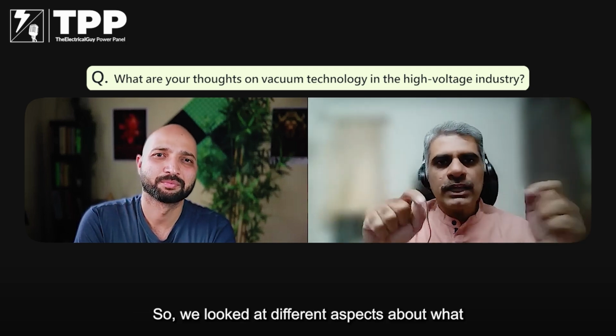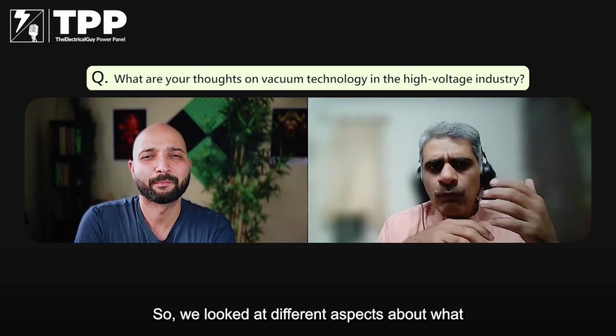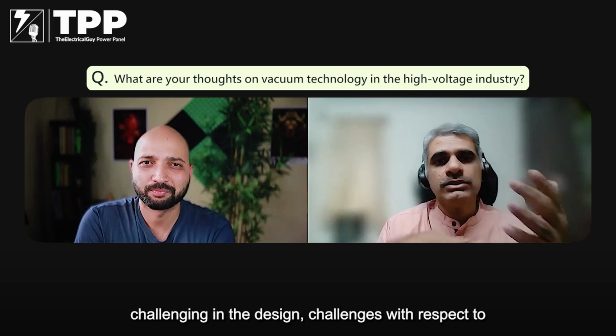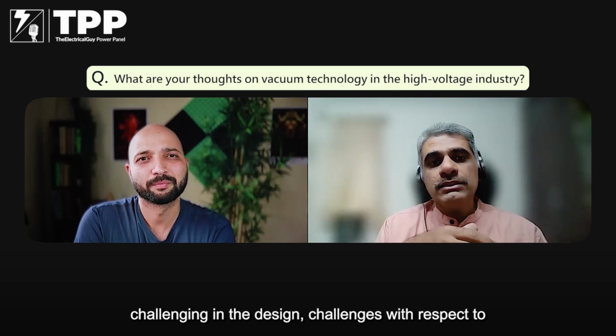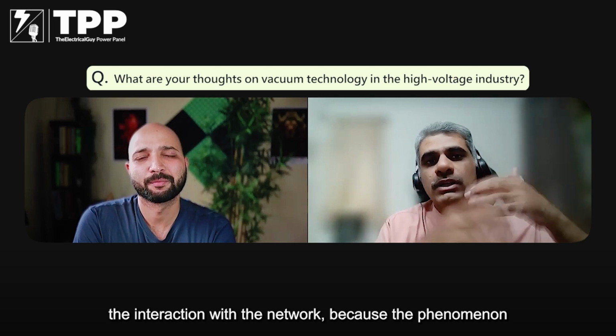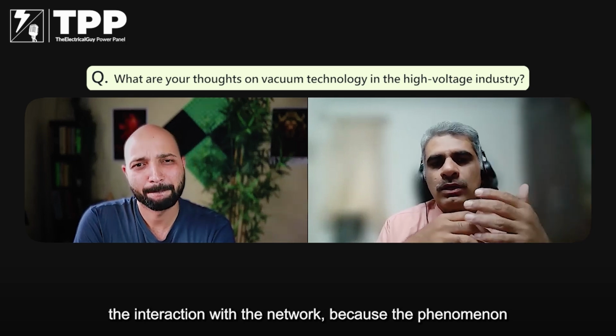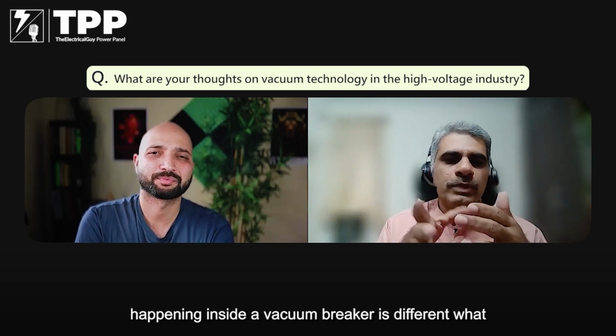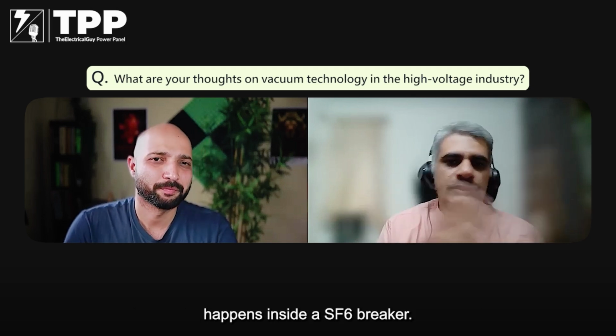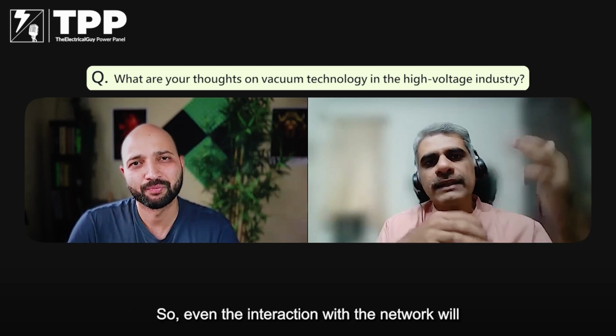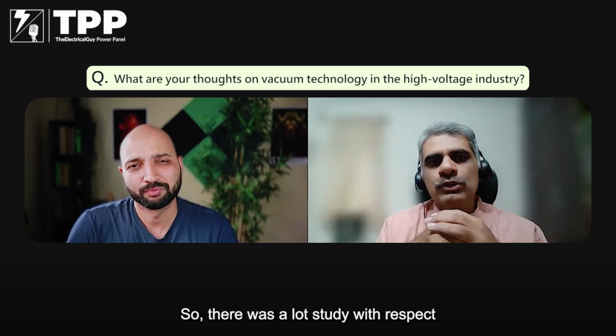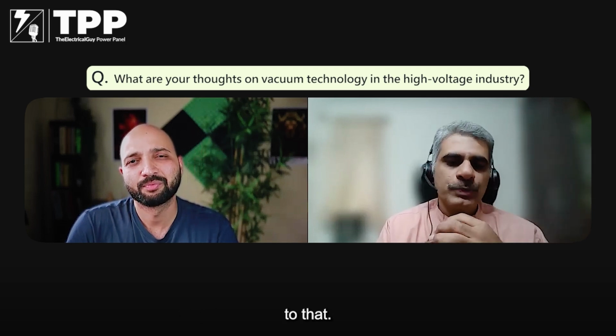So we looked at different aspects: the challenges in manufacturing of the breakers, challenges in the design, and challenges with respect to the interaction with the network, because the phenomenon happening inside a vacuum breaker is different from what happens inside an SF6 breaker. So even the interaction with the network will be different. So there was a lot of study with respect to that.